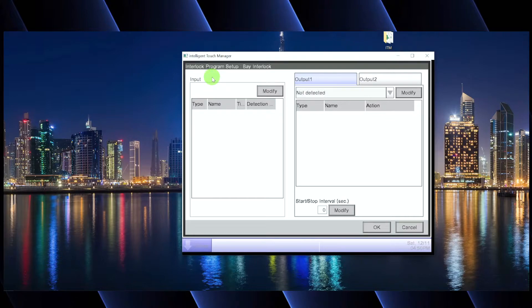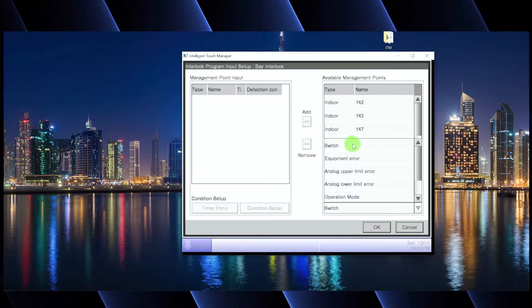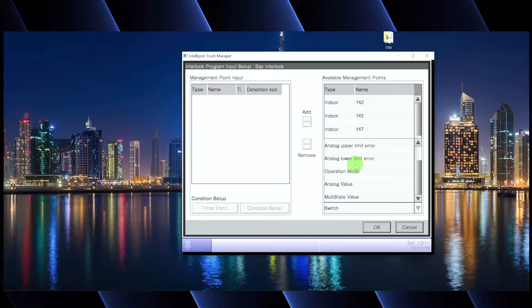Click the program name you created and go down to Edit. We're going to program the input — this is the 'if' statement: if this happens, then the output happens. Click Modify. Before we grab anything from the available management point section, we need to tell it what type of input it is: a switch on/off, an error or alarm status, an analog upper limit, an operation mode, or just an analog value. You have a lot of things to choose from.